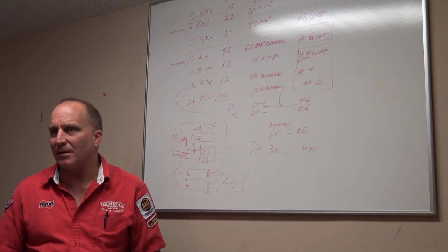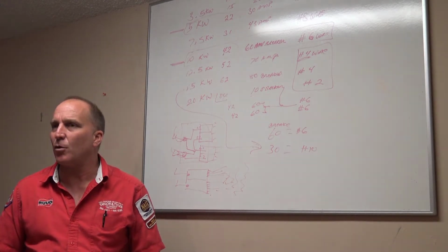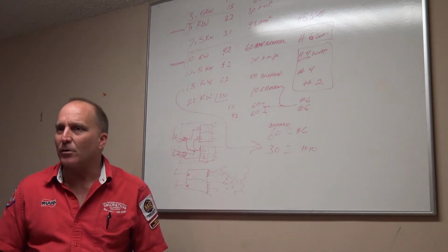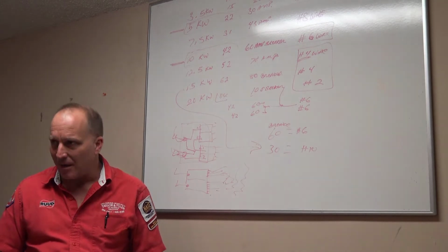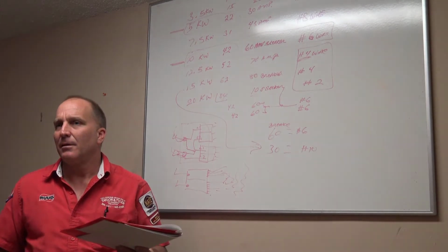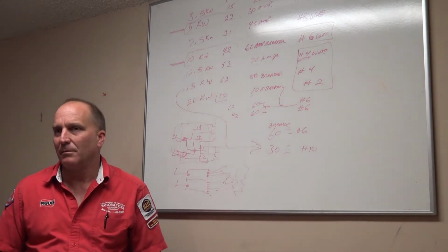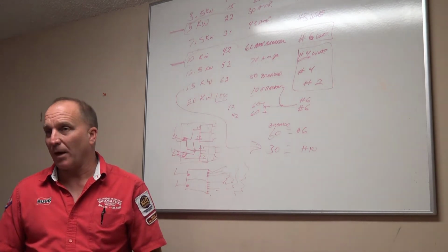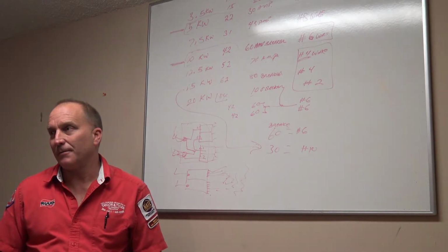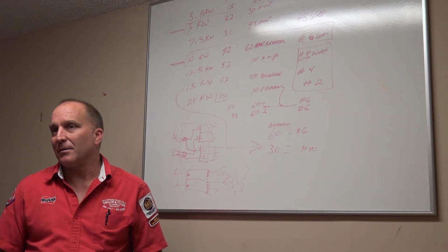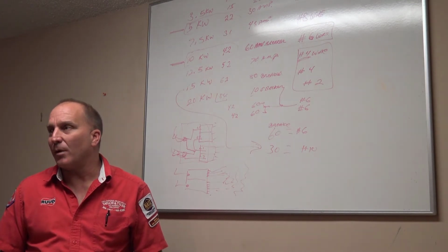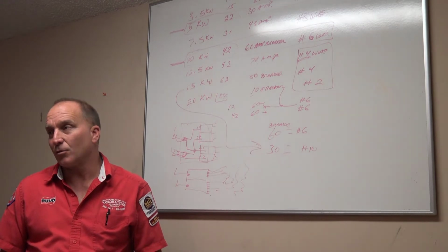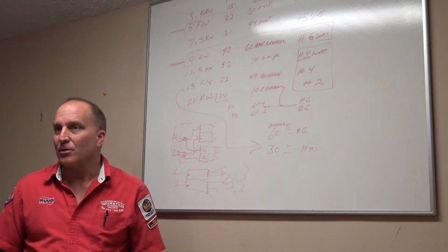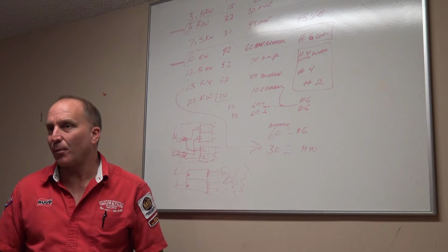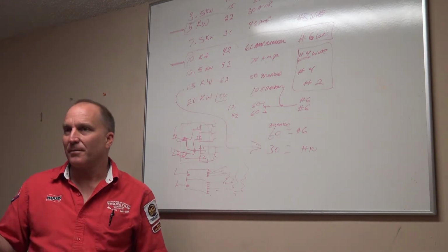If you do an electric heat system, what is the number one thing you have got to check? Breaker sizes, wire sizes, heat, amps, burning stuff. Okay? Not tripping breakers, burning stuff. If I got 60 amps drawing into a 40 amp breaker, I don't have to worry about burning. It's going to trip the breaker. Okay? So if you get there and you have a tripped breaker, it's high amperage.